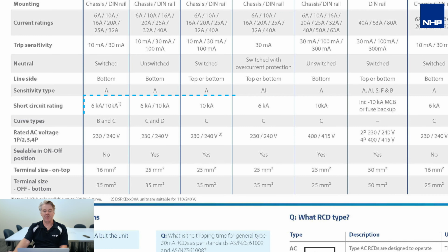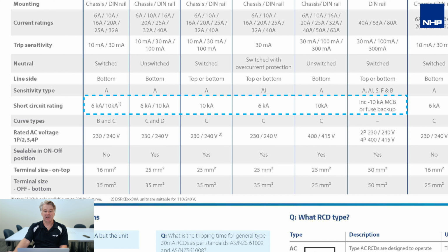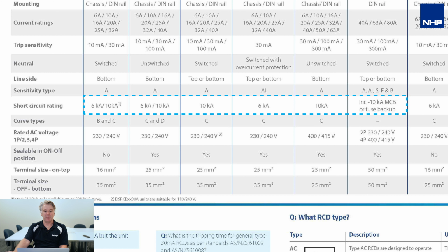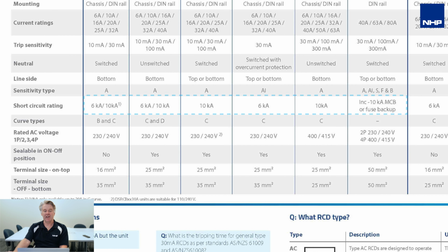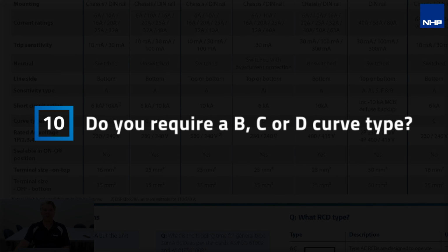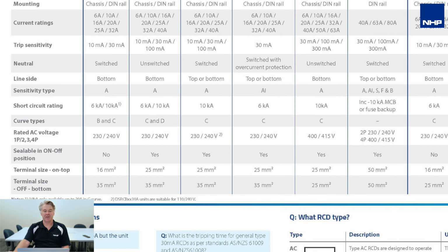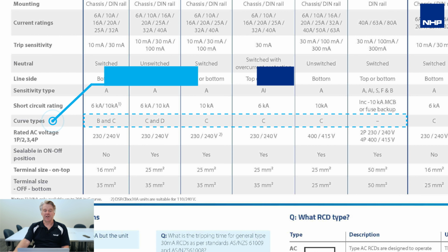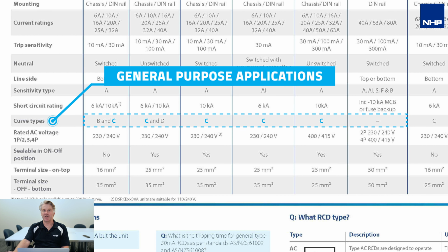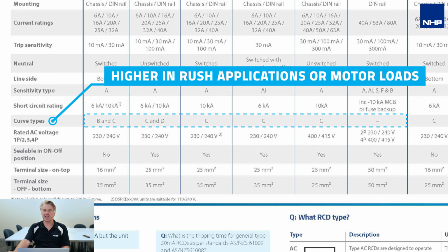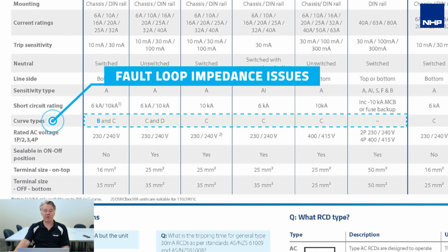The next one, of course, is the fault level. Is it a high prospective fault level where you may require a 10 kA device, or is it just 6 kA, or your fault level is even lower? So make sure you choose the required kA short circuit rating for your RCD protection if it's an RCBO. Then of course the curve type. Do you require a C curve, a B curve, or a D curve, depending on the type of load you're requiring? General purpose applications just require a C-type curve. But if you have higher inrush applications or motor loads, you may require a D curve. If fault loop impedance is an issue, you may require a B curve type device, as you can see here.